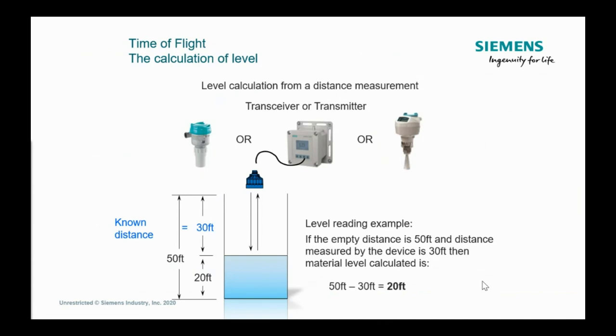The key takeaway here is this. If you're having a problem with level and your level is off by a little bit, make sure that you have the right distance programmed in as to what empty is on the tank. If that 50 isn't actually 50 and it's 48, it's going to throw off your level measurement, which is a calculated value. The other thing that I've found, and this is a tip and trick for the people actually diagnosing or troubleshooting.